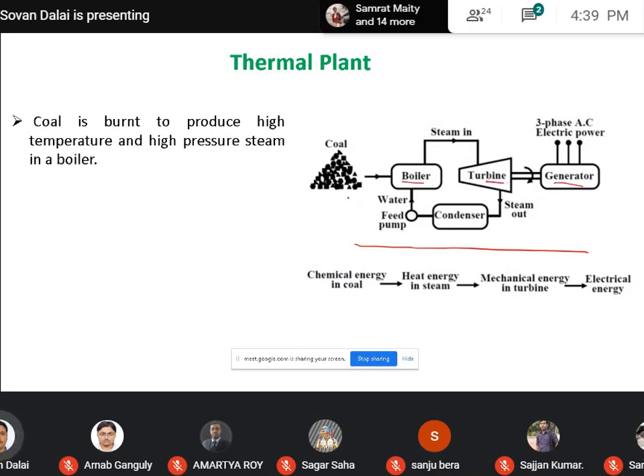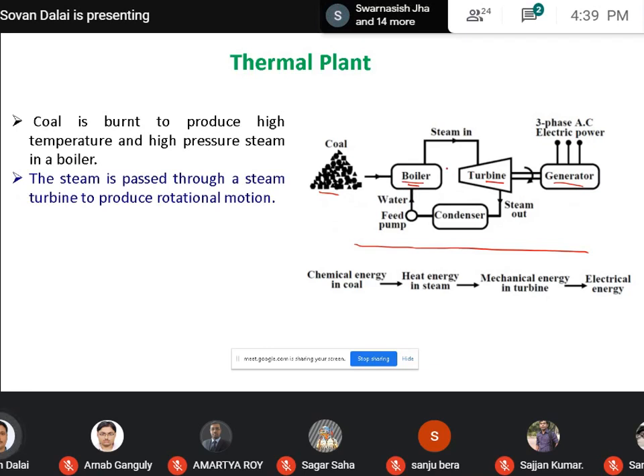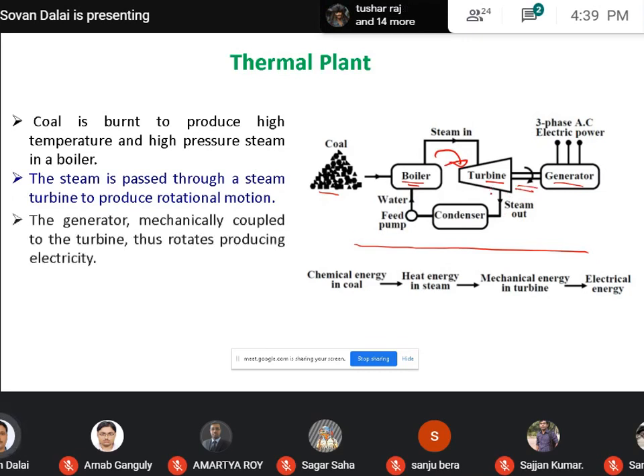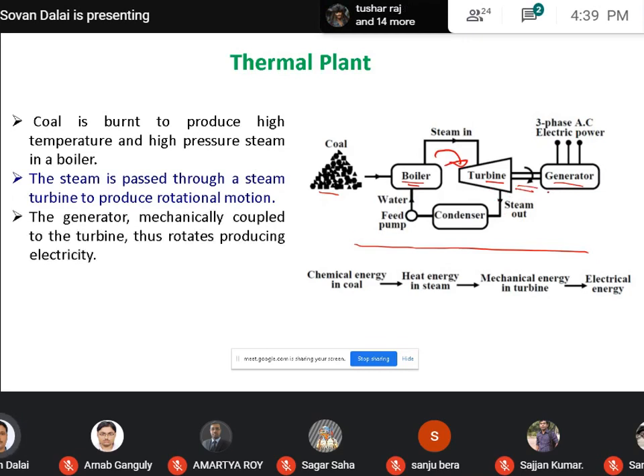In most thermal power plants, coal is used as the fuel. Coal is burned to produce high temperature and high pressure steam inside the boiler. Then the steam is passed through a steam turbine that produces a rotational motion, and this turbine acts as the prime mover of the generator. The generator is mechanically coupled to the turbine and is thus rotated, and the generator produces electricity, that is, three-phase AC electrical power.